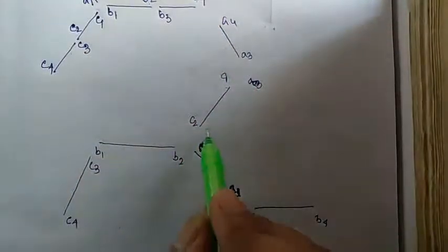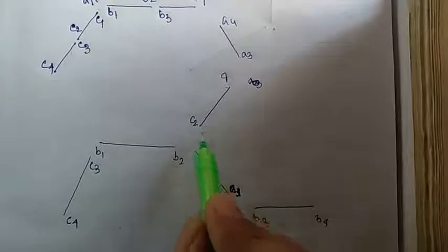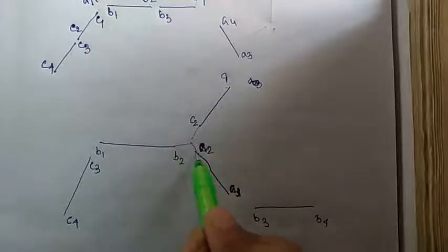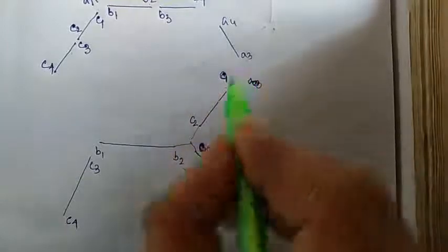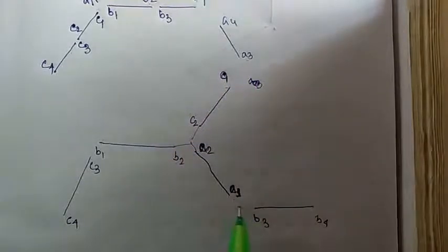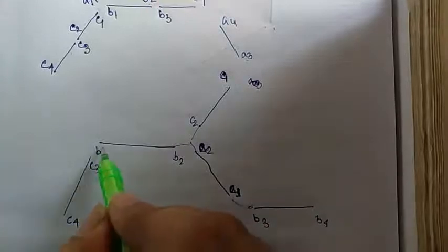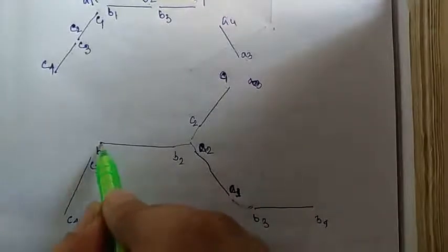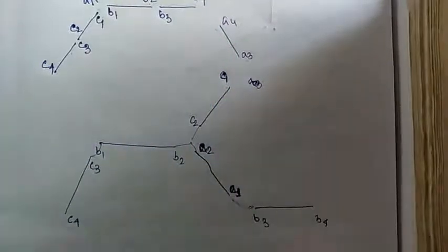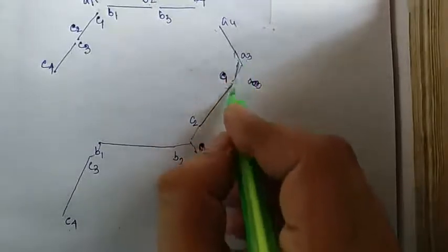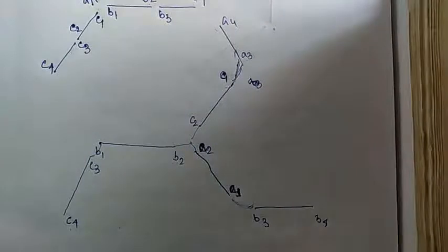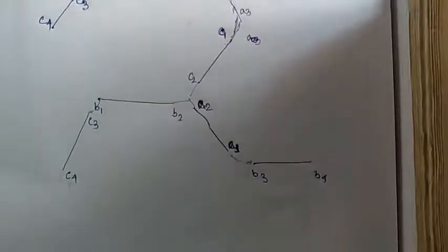Here A2, B2, C2 are connected to form a neutral. Now C1 is connected to A3, A1 is connected to B3 and B1 is connected to C3. A4, B4 and C4 terminal position is unchanged. So this is the zigzag connection, and now the phase displacement is 0.